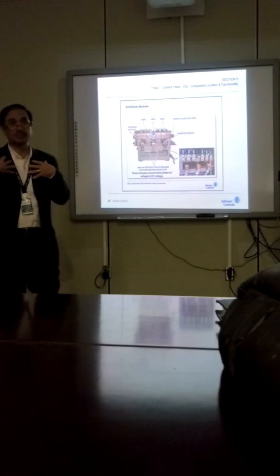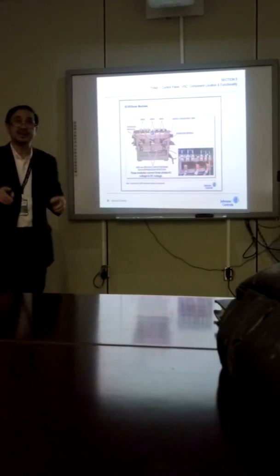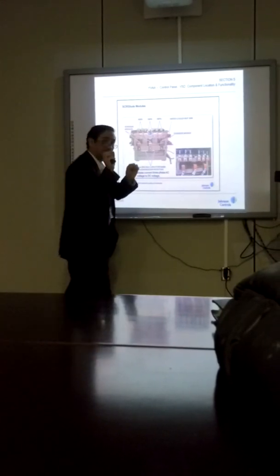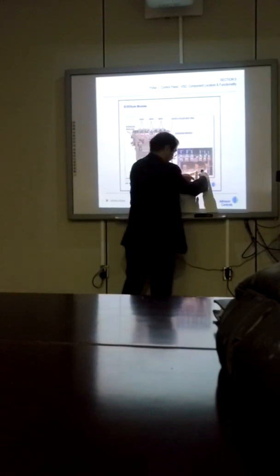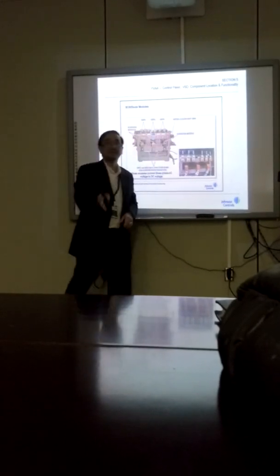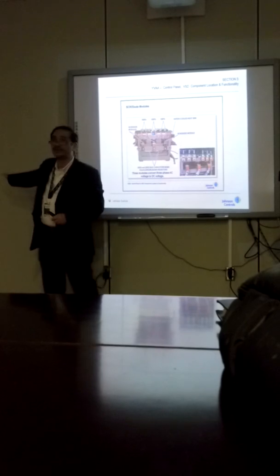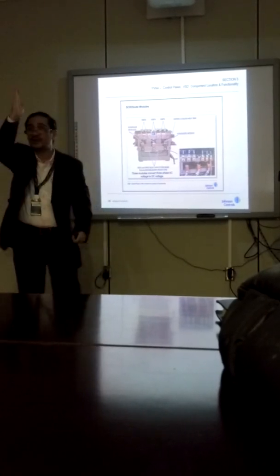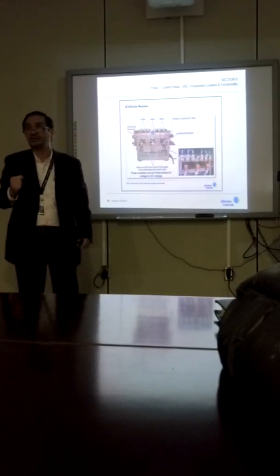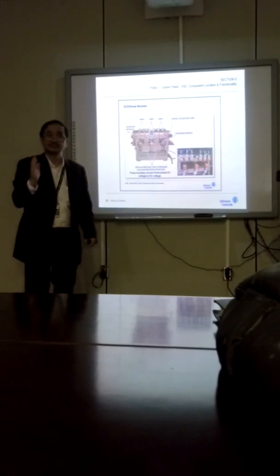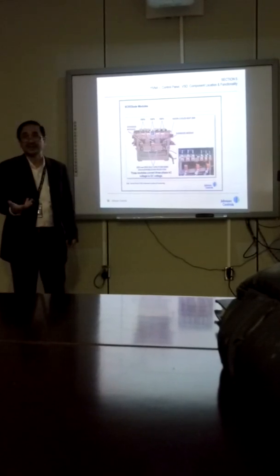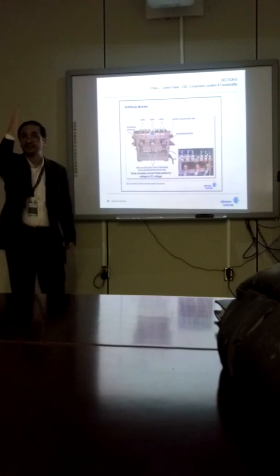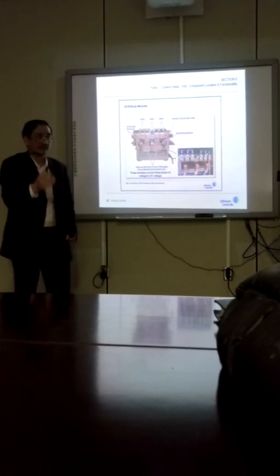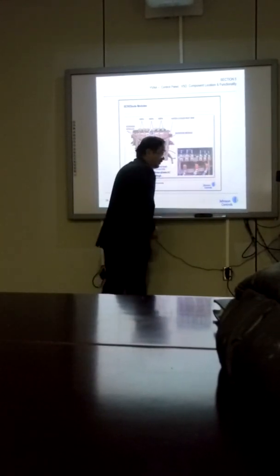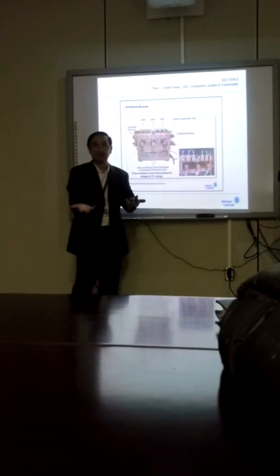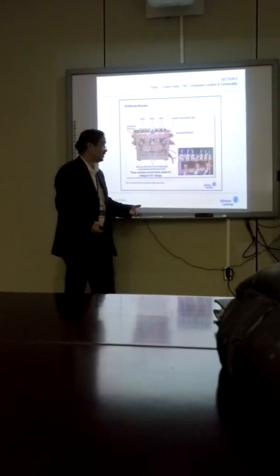Wait until it drains. But even after 15 minutes, to be safe, still put your meter here. Because you'll never know, maybe your disconnect switch has a mechanical failure. Maybe one line is still connected when you shut it down. One of the mechanical disconnects, at times they fail in one of the lines. And somehow, maybe one of these is alive, and then you suddenly touch it without thinking. So it's a safety reason.